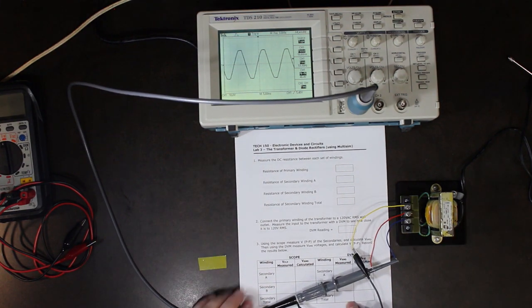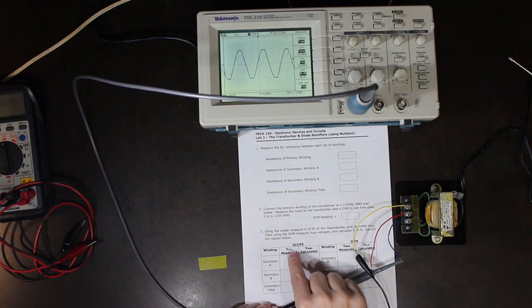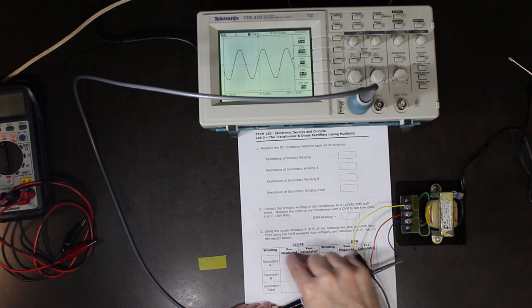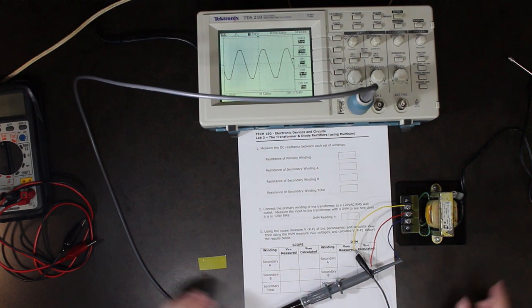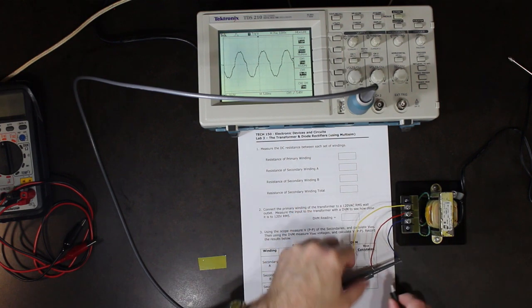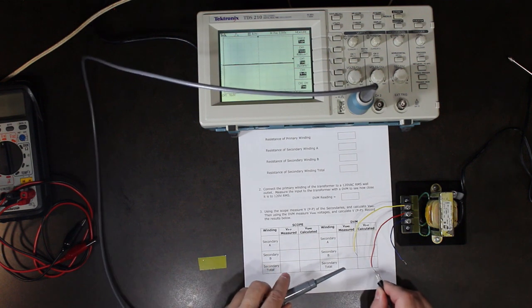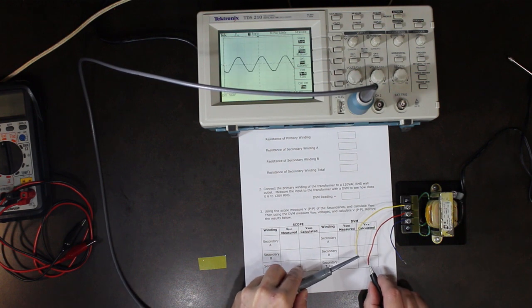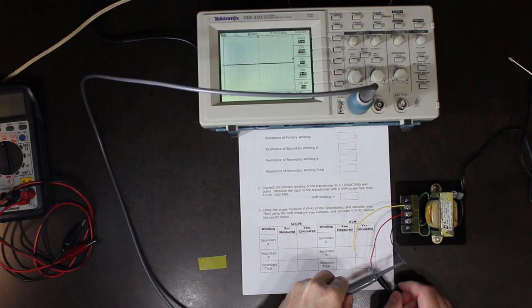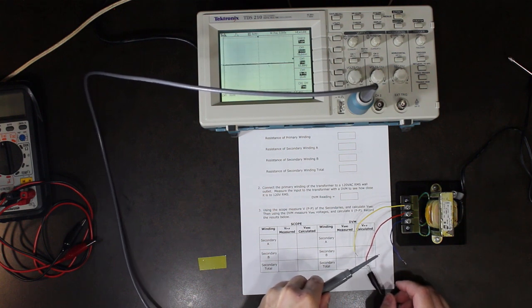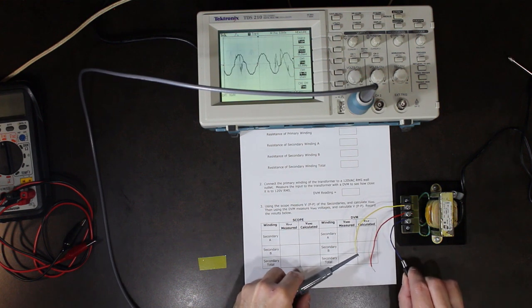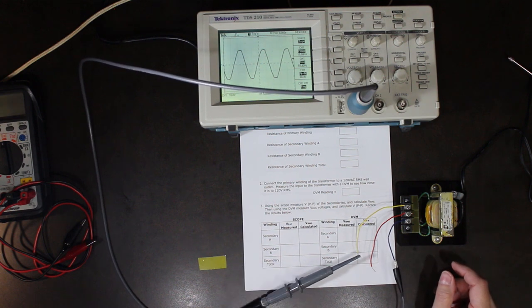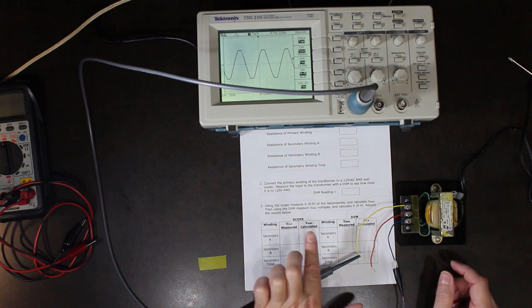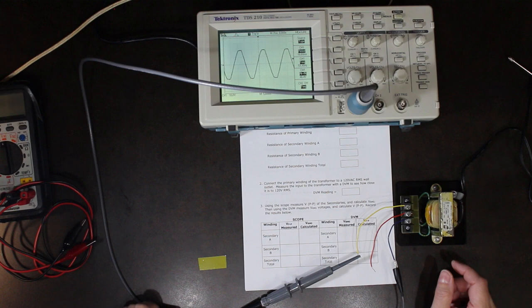So now when we're looking at this, we have total secondary peak-to-peak 40.4. Secondary B was 20.4, secondary A 20.4. You can now take those peak-to-peak measurements and turn them into an RMS value. So one more time: secondary A peak-to-peak 20.4, secondary B 20.4, and then across the full secondary 40.4. Okay, so we've got those measurements. These you can calculate - we took those measurements, and those ones you can calculate.